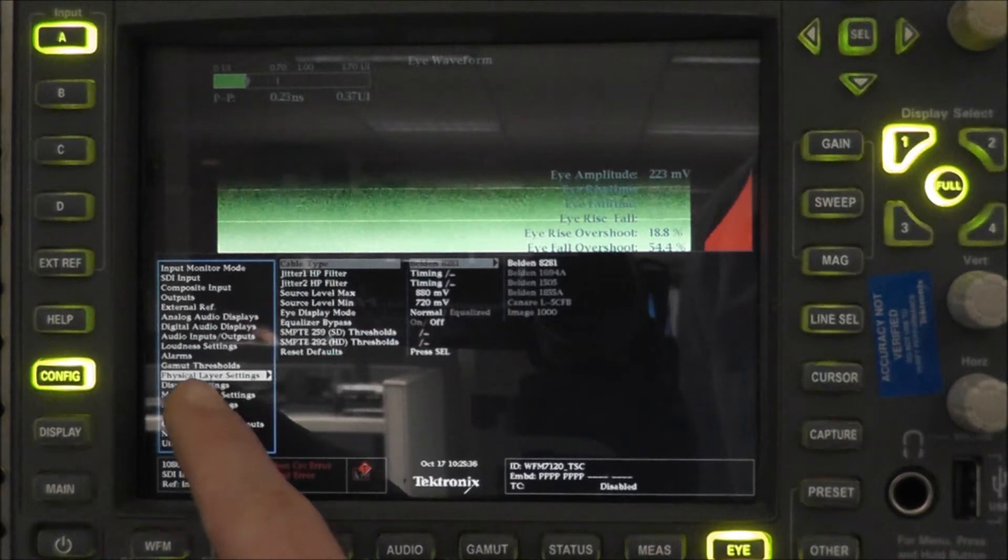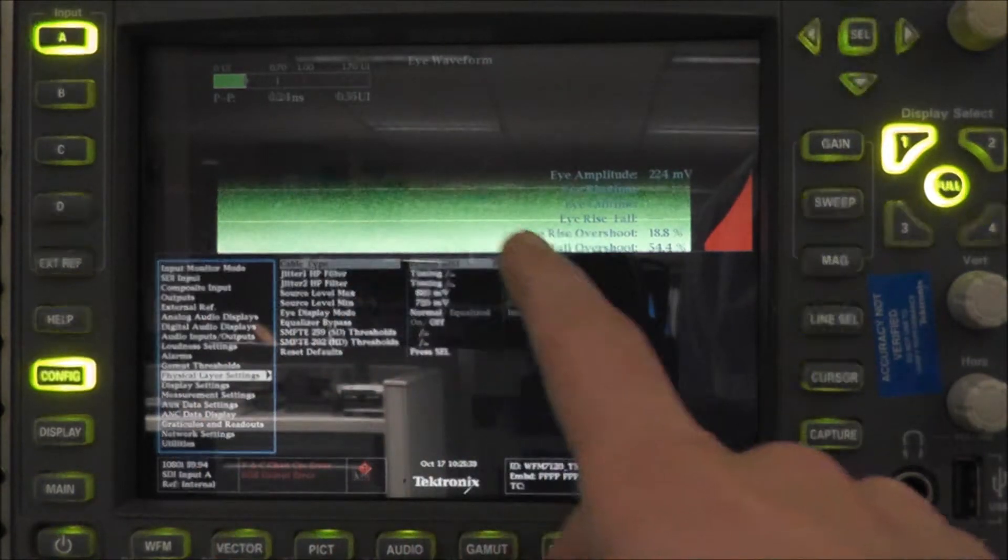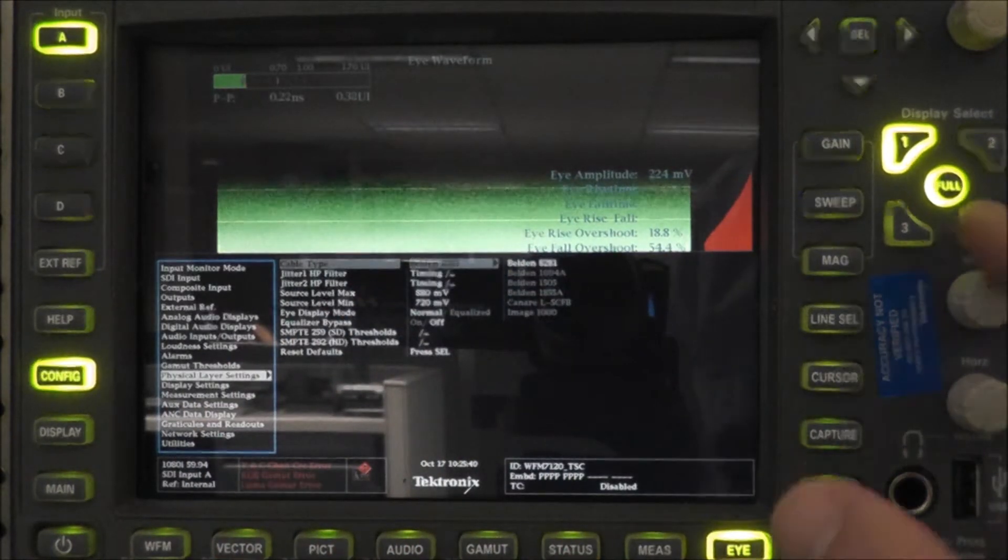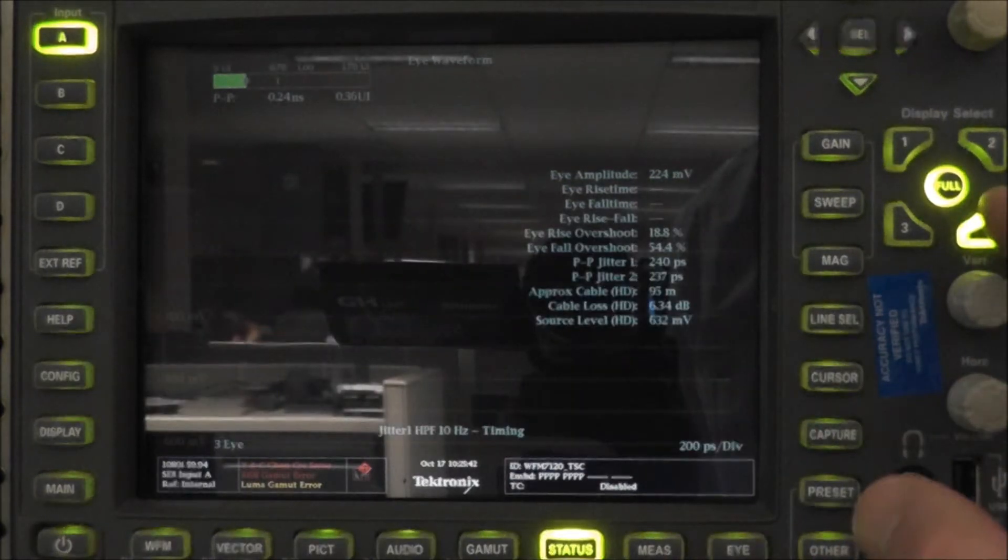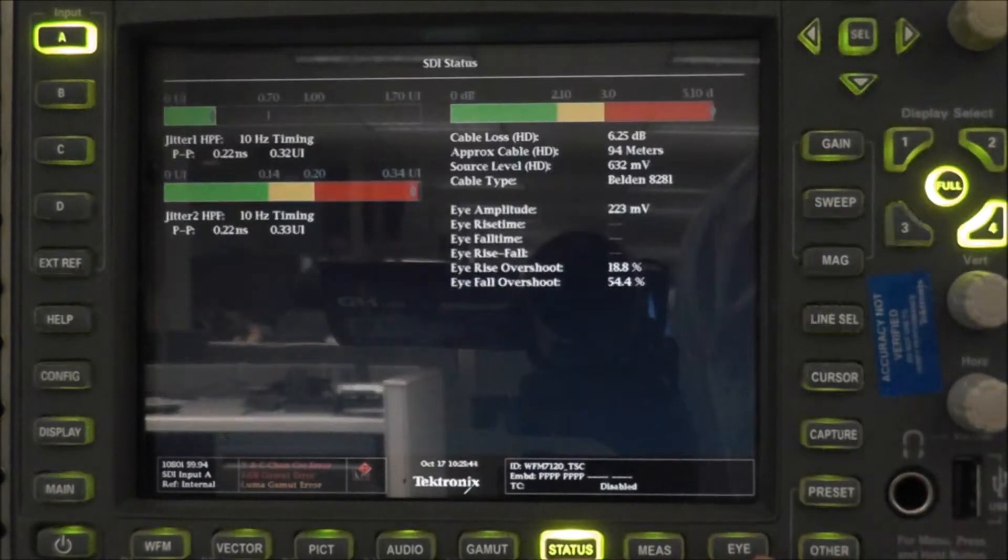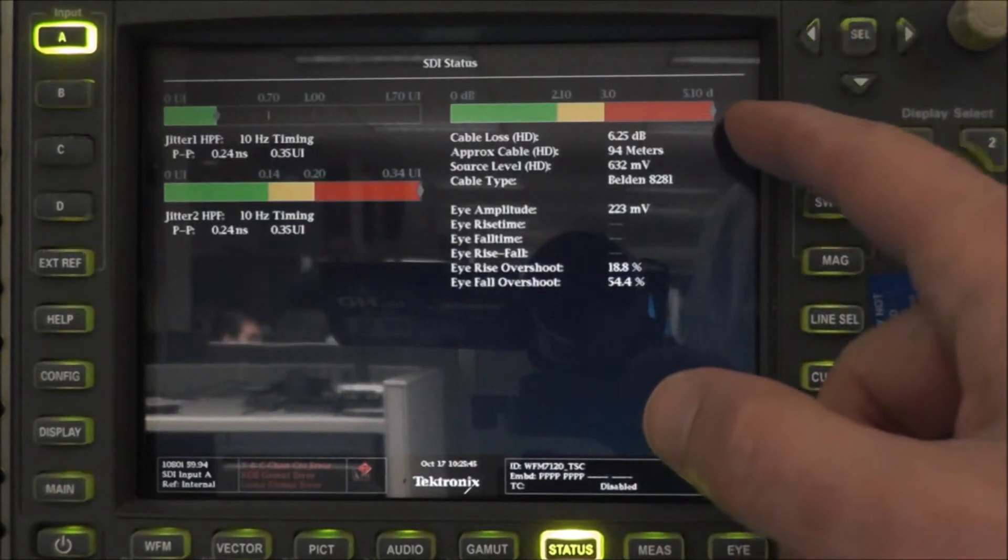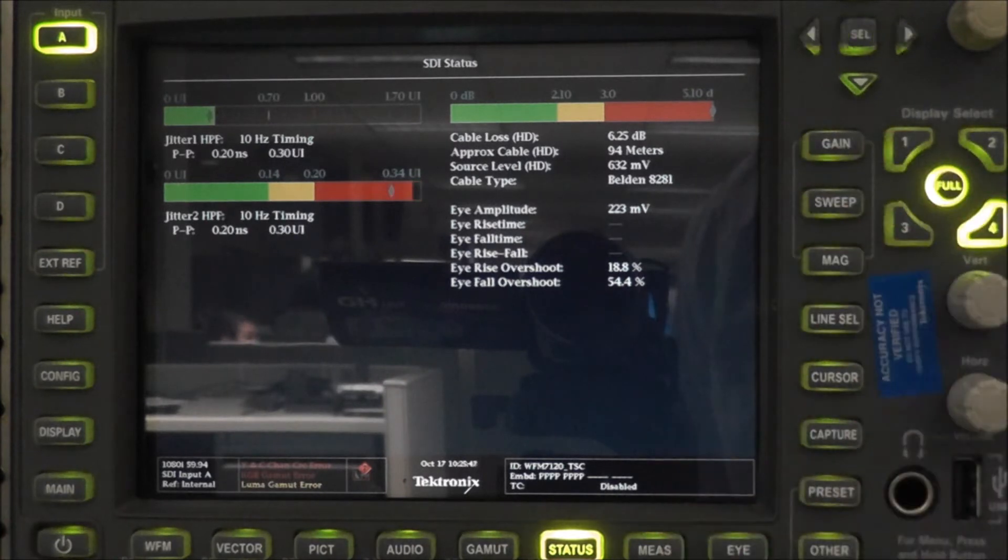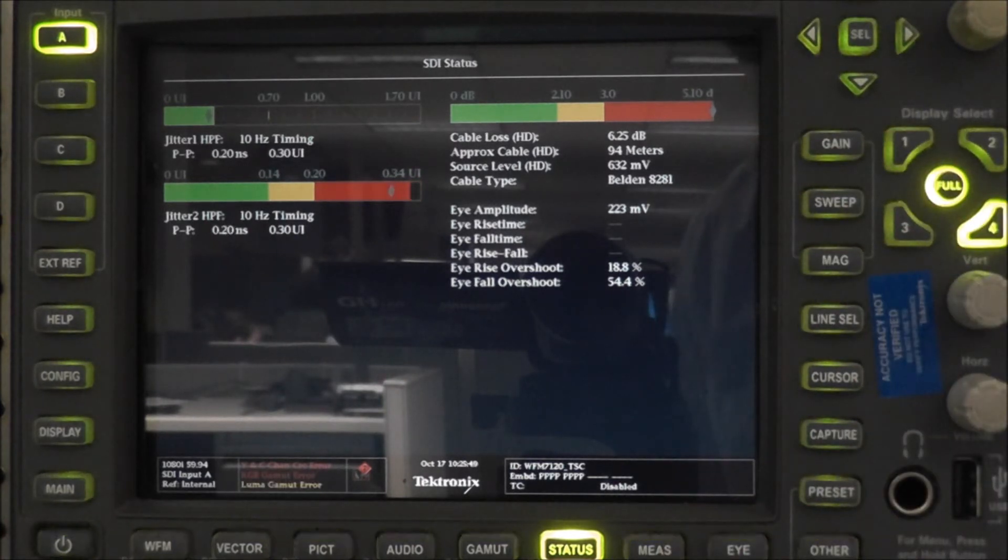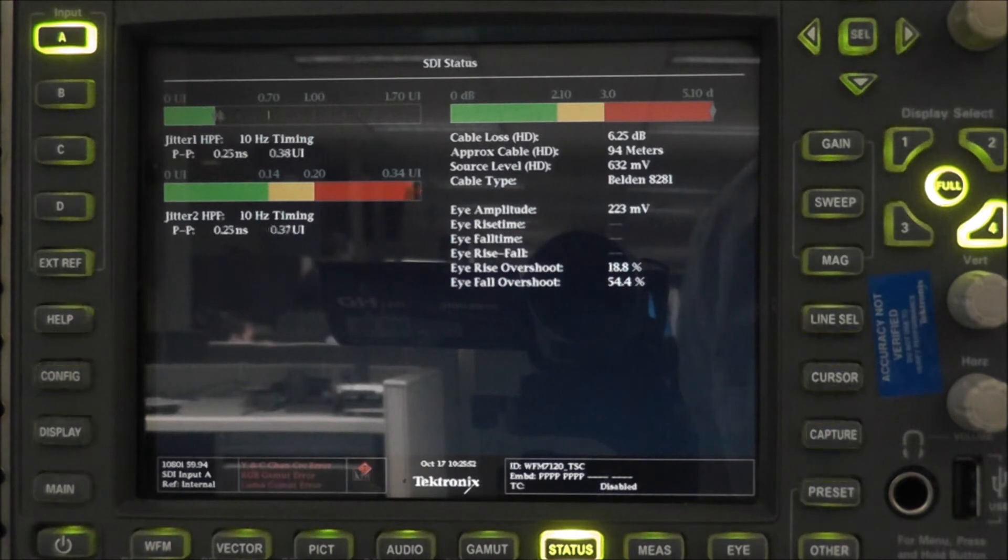As you can see, this unit, the WFM7120, is configured with an eye that allows us to also set up any kind of cable type. From there, we can go to our SDI measurements, which is included in the eye, and see an approximate cable distance of 94 meters.